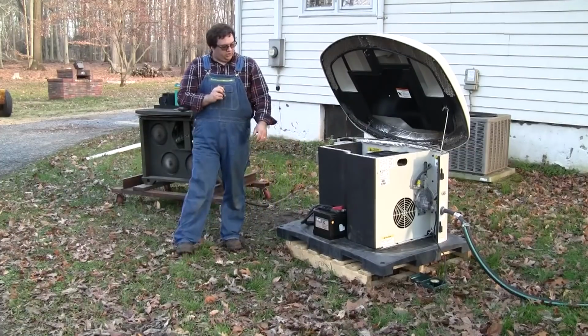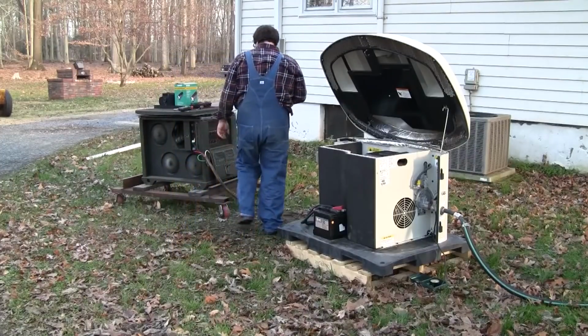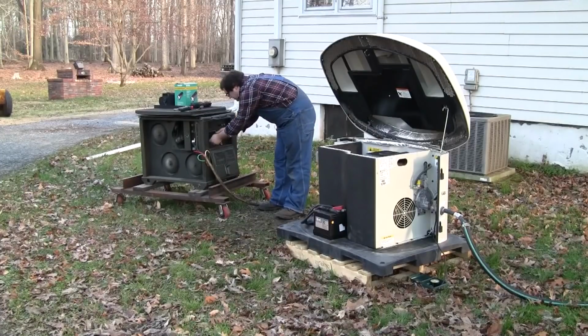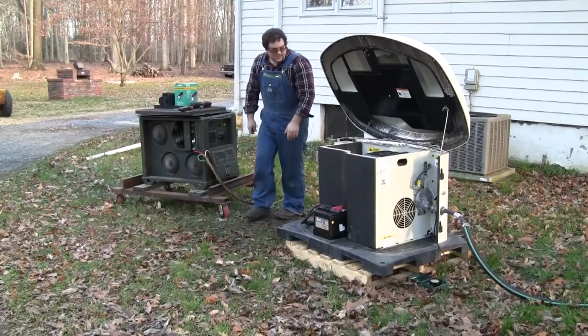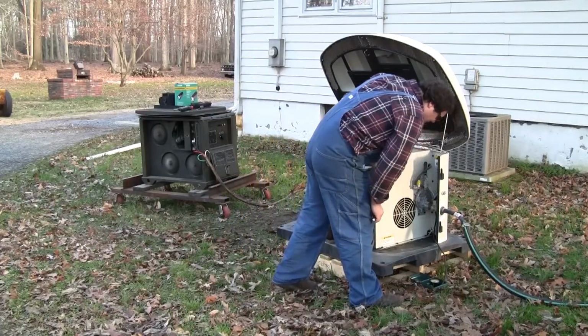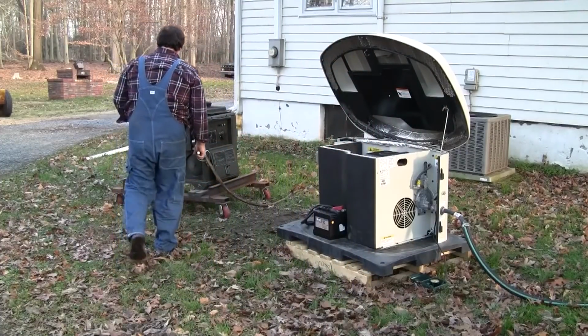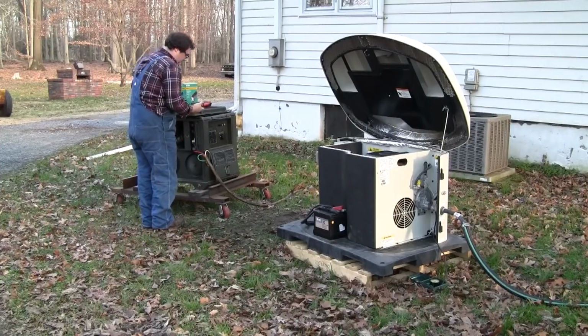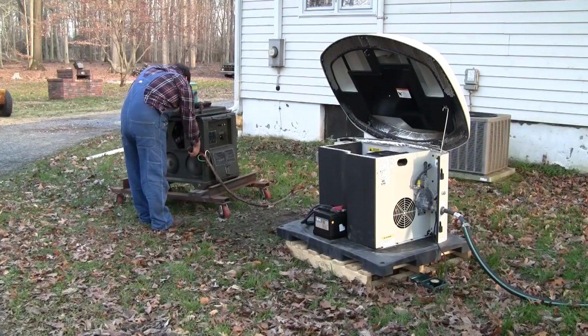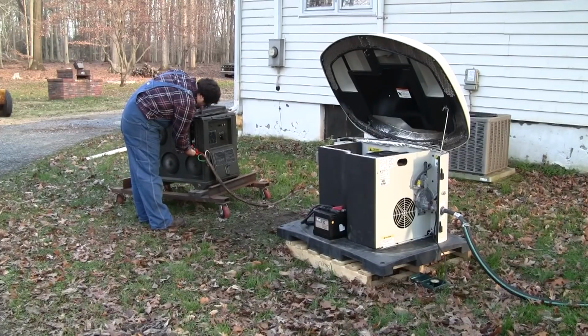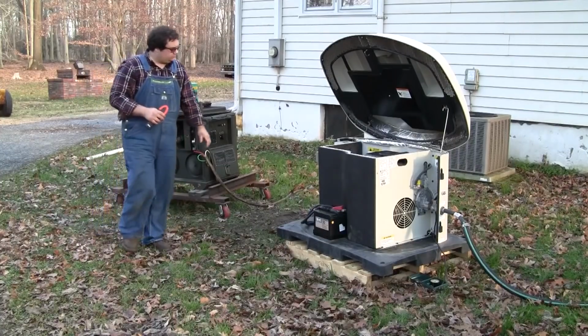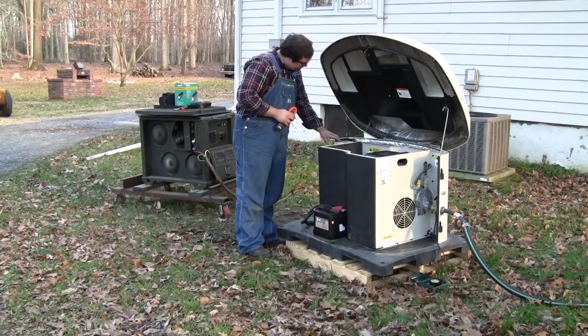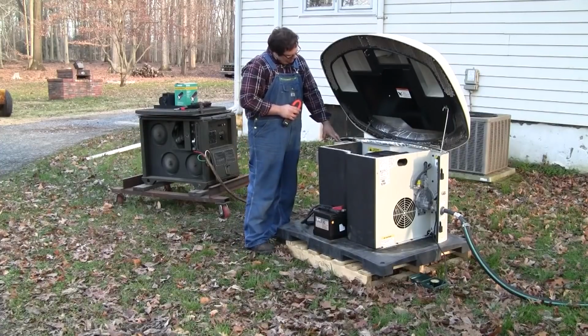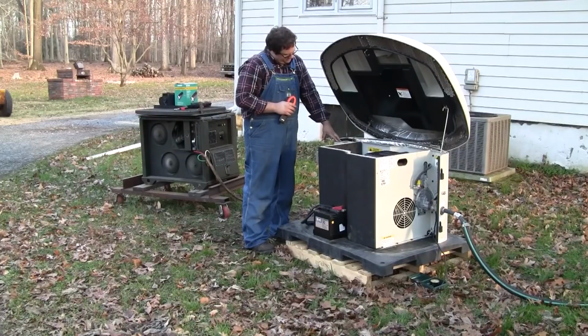Okay, the engine should be fully warmed up at this time, so let's increase the load. So we got 3 kilowatts on it now. Let's go to 6. Let's go to 9. It's 9 kilowatts. Fuel pressure is about 5.5 inches of water column. We're drawing right about 40 amps, 39.7, 39.8, right about 40 amps at 240 volt. And the generator's output is 240 volts, 239, 240 at 60 hertz on the nose.